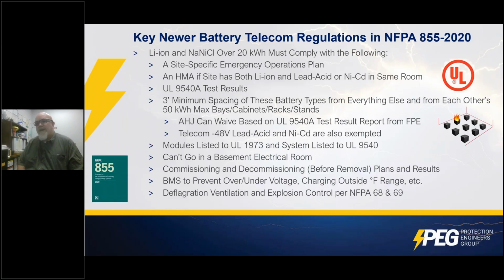That is not a battery monitoring system. That's a battery management system. There's a BMS built into these batteries to prevent them from being overcharged, undercharged, over-discharged, charging outside their temperature range, etc. And you have to have deflagration, ventilation, and explosion control per NFPA 68 and 69. So that's the lithium-ion specific stuff. Next slide.